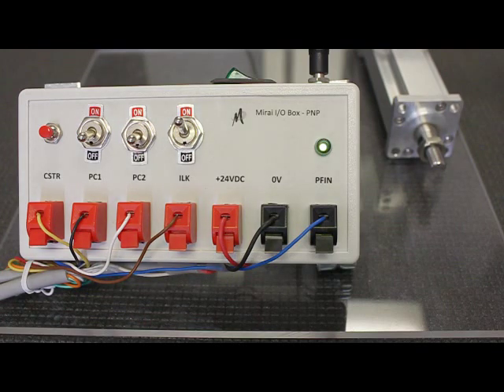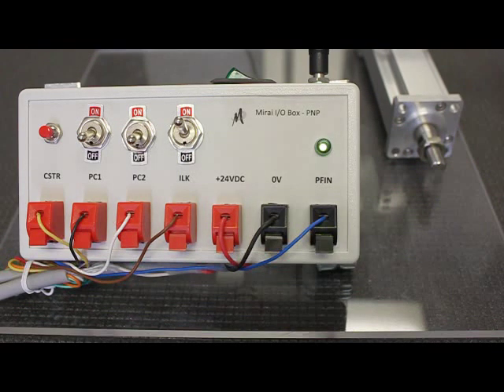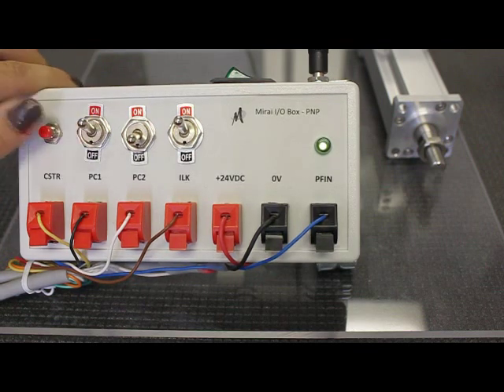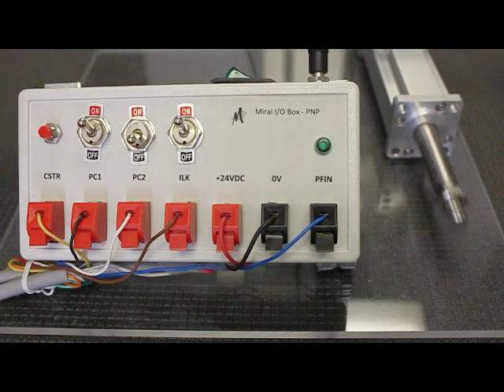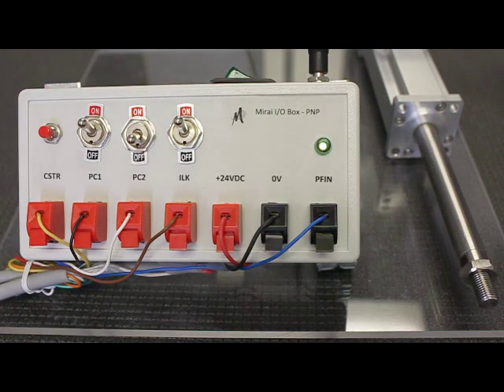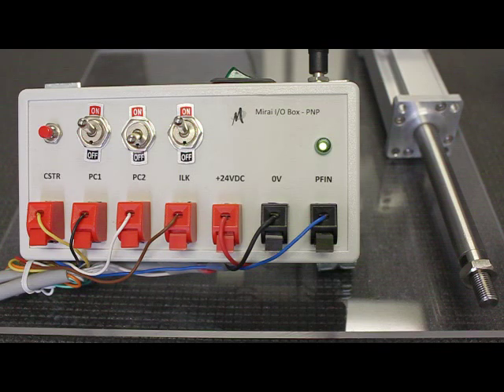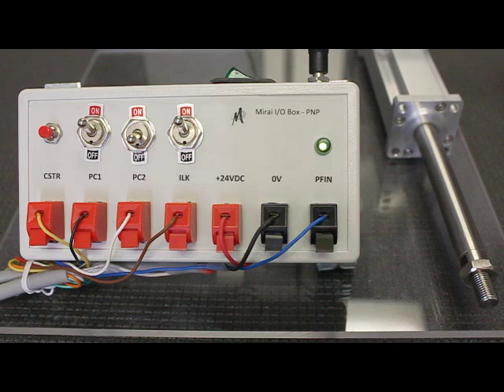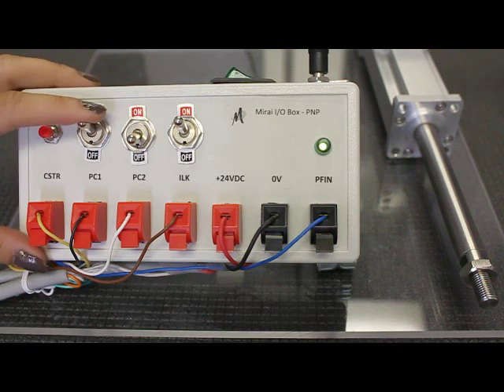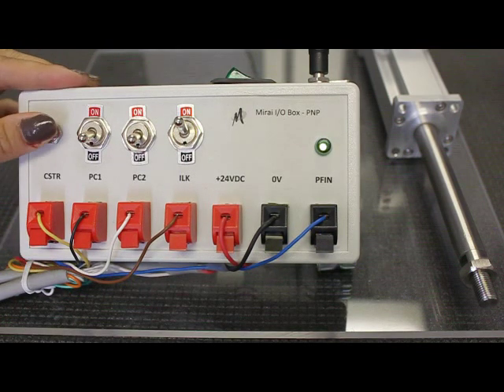To run move 1 simply apply power to PC1 input and send the start pulse. We can see that the actuator makes a move with smooth acceleration and deceleration just like we programmed it to. Also note that the PFIN output comes on to indicate that the position is finished.